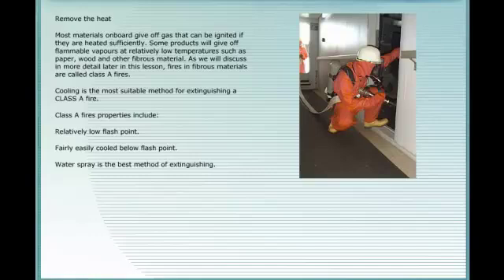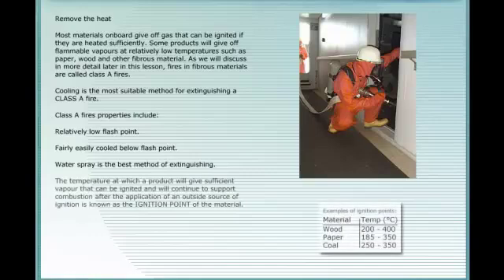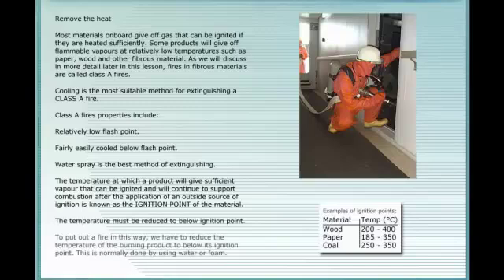Water spray is the best method of extinguishing Class A fires. The temperature at which a product will give sufficient vapour that can be ignited and will continue to support combustion after the application of an outside source of ignition is known as the ignition point of the material. To put out a fire in this way, we have to reduce the temperature of the burning product to below its ignition point. This is normally done by using water or foam.